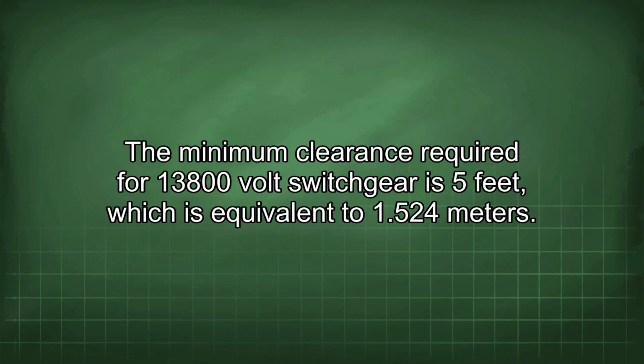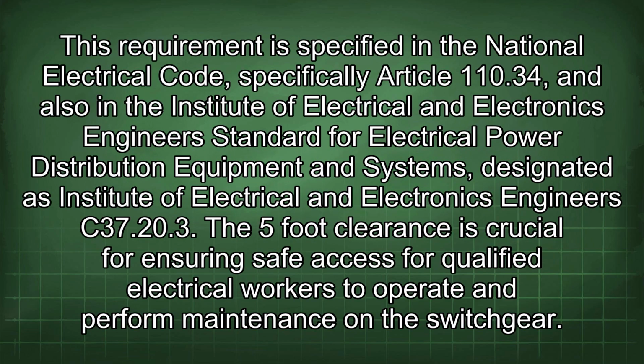The minimum clearance required for 13,800 volt switchgear is 5 feet, which is equivalent to 1.524 meters. This requirement is specified in the National Electrical Code, specifically Article 110.34, and also in the Institute of Electrical and Electronics Engineers Standard for Electrical Power Distribution Equipment and Systems, designated as Institute of Electrical and Electronics Engineers C37.20.3.